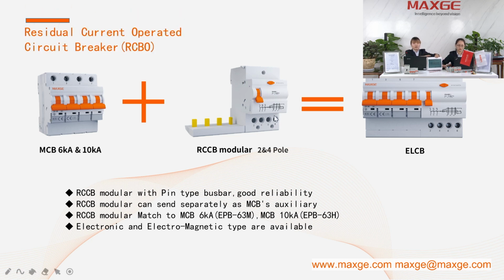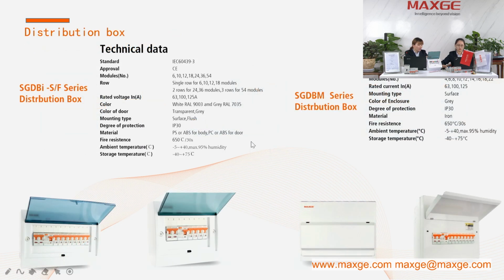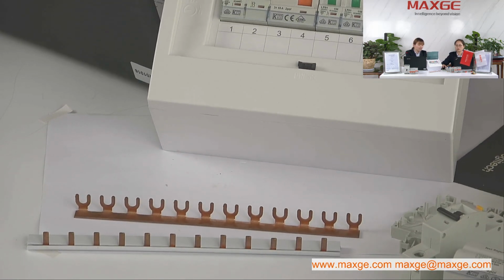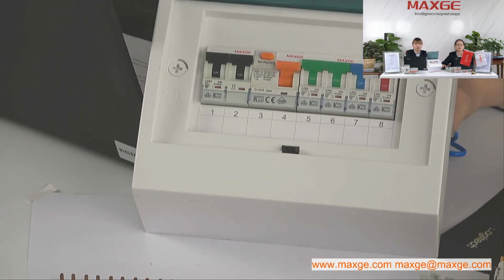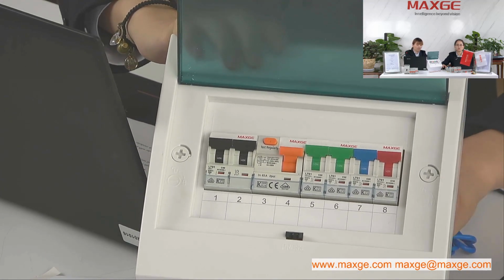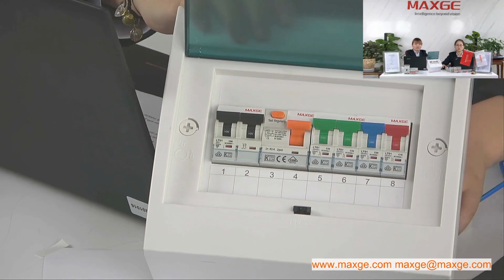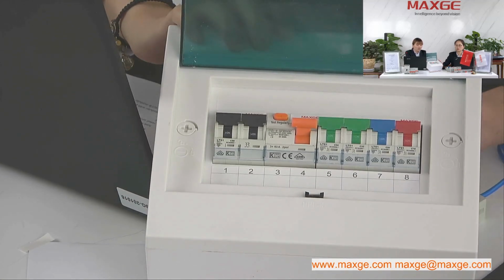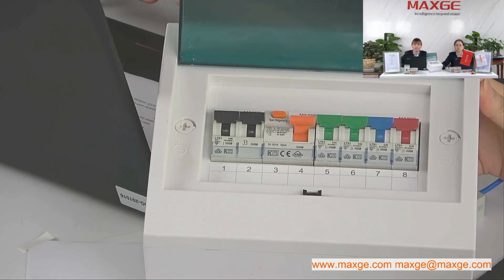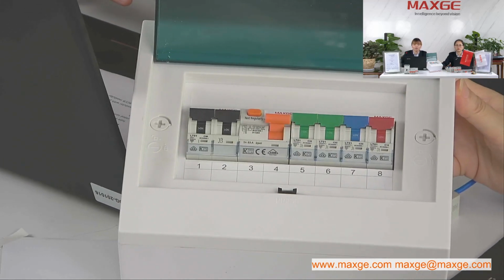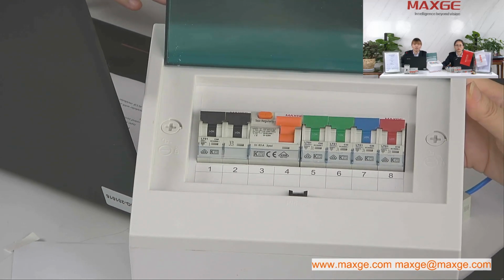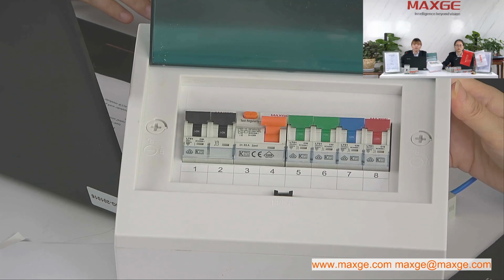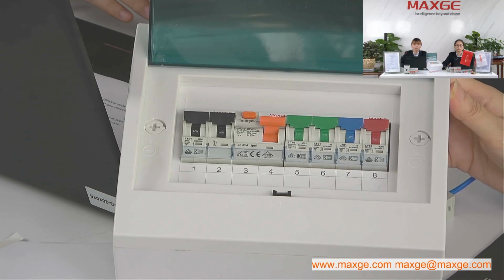We have the French plastic type and the UK metal type. It is in compliance with IEC 60439-3 standard. We have got the TUV certificate. Its ambient temperature is -5 degrees Celsius to 40 degrees Celsius, and the storage temperature is -40 degrees Celsius to 75 degrees Celsius.